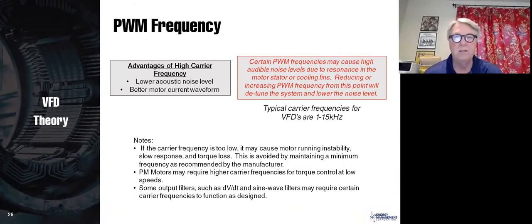What are the advantages of high carrier frequency? The higher the carrier frequency, the lower the acoustic noise. You know that drives tend to sing. They have that kind of ee noise. That noise is at the carrier frequency. And if you change the carrier frequency, that noise will change. And the higher the carrier frequency in general, the lower the noise level. So by increasing the carrier frequency, that drive will become quieter. Again, not the drive itself, but the motor operating on the drive will be quieter. And as you can see, you get a slightly improved motor waveform. And there are some other things in there that you can read later.